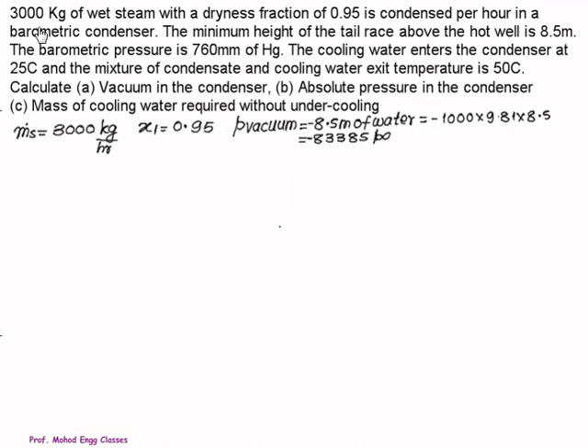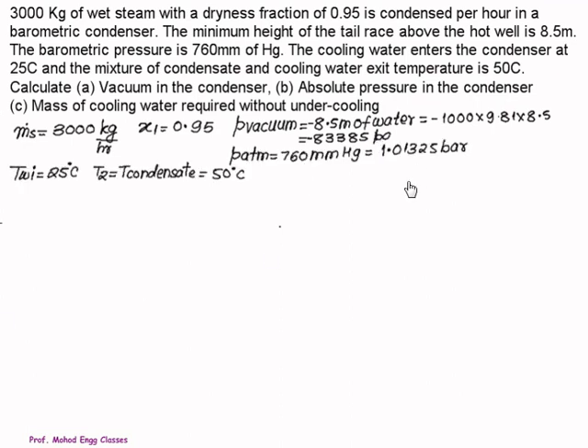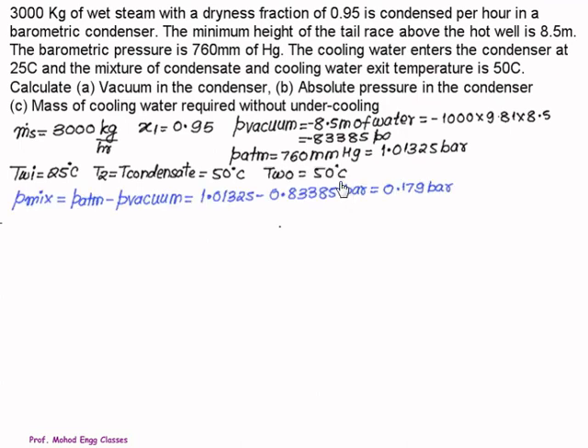We have mass of steam 3000 kg per hour. Inlet dryness fraction is 0.95. This 8.5 we treat as a vacuum of minus 8.5 meters of water. Any pressure can be converted using the formula rho*g*h. Rho of water is 1000, g is 9.81, and height is 8.5, which is approximately equal to minus 83,385 Pascal. Atmospheric pressure is 760 mmHg, which is approximately 1.01325 bar. Cooling water enters at 25 and temperature of condensate equals 50 degrees Celsius, as well as the temperature of water leaving the condenser is 50 degrees Celsius.